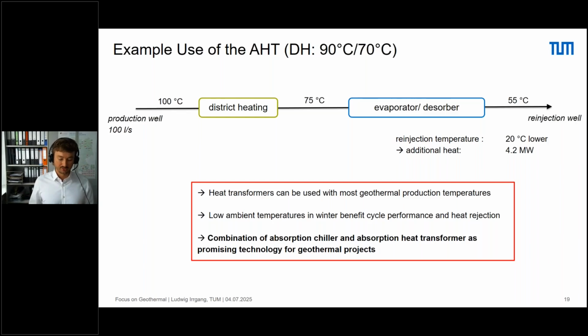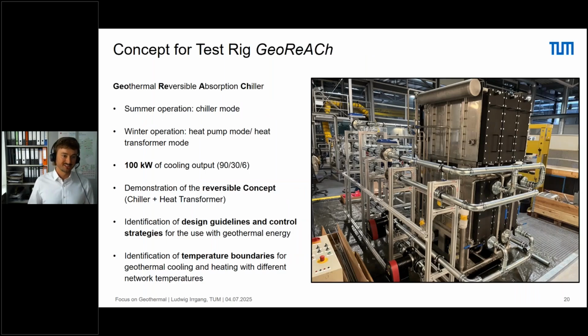So what we wanted to investigate is how we can combine an absorption chiller and an absorption heat transformer into one machine. And that's where the concept for our test rig came from. GeoReach, which is the name of the test rig, stands for Geothermal Reversible Absorption Chiller. And as I explained, we want to have the chiller mode in the summer operation, and the focus is more on the heat transformer mode and winter operation. We designed the machine for 100 kilowatts of cooling output. And the idea is to demonstrate the reversible concept, which means that we have the chiller in the summer months and the heat transformer in the winter months.